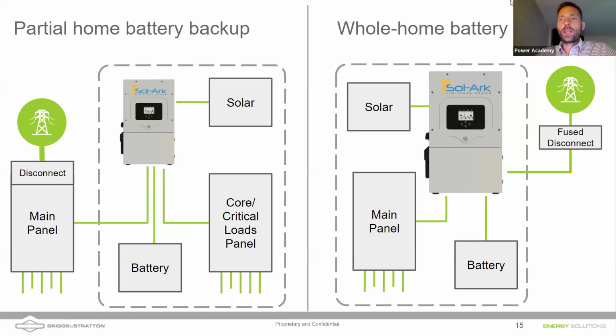And so if you are backing up the entire house during a grid outage, the inverter will isolate itself from the grid. So you could have a fuse disconnect or a breaker disconnect here, 200 amps of pass through. But all of the power coming from the grid actually would pass through the inverter. And so now the inverter is backing up the entire main electrical panel of the house. So all the loads in the house.